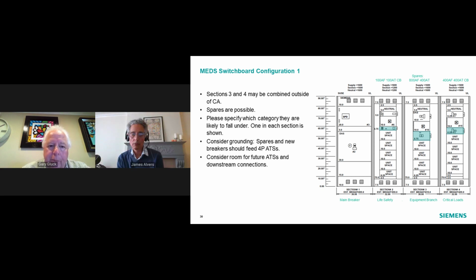All right. Just a couple of final words about this configuration, and then we'll move on to the final topic of switchboard size. Sections 3 and 4 can be combined outside of California. Those are going to be your critical and your equipment. And when you're dealing with spares, please let us know what category they're going to be applicable to. It absolutely makes our life so much easier than trying to guess, because inevitably we're going to guess wrong. And then, as we mentioned before, consider grounding. Spares and new breakers should feed 4-pole transfer switches, and consider room for future ATSs and downstream connections.